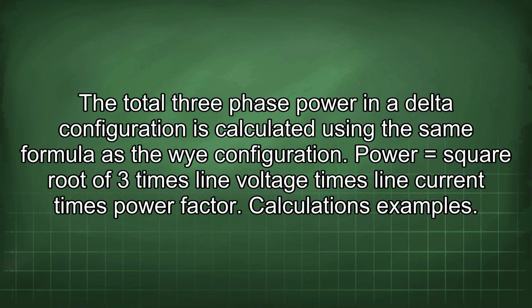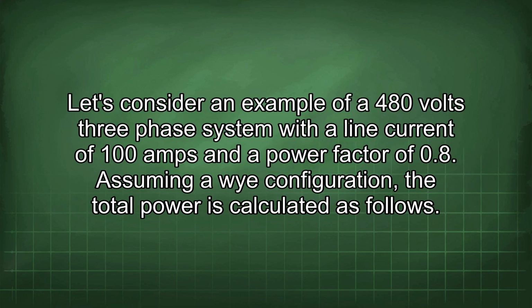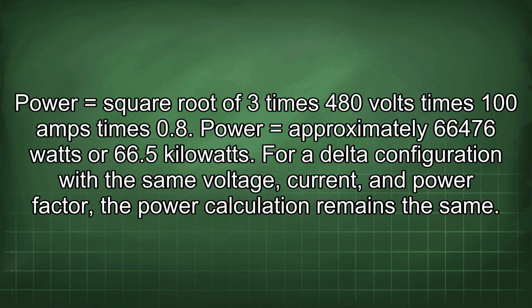Calculation examples. Let's consider an example of a 480 volts three-phase system with a line current of 100 amps and a power factor of 0.8. Assuming a Y configuration, the total power is calculated as follows. Power equals square root of 3 times 480 volts times 100 amps times 0.8. Power equals approximately 66,476 watts or 66.5 kilowatts.